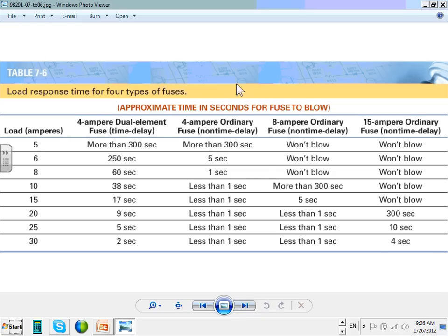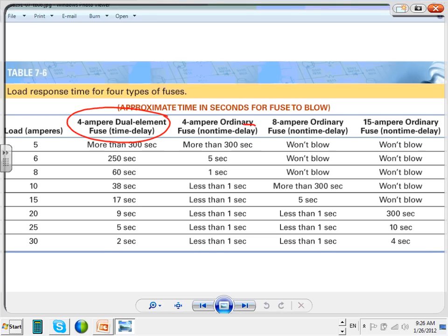This is just how fast the overcurrent protective device can trip, guys. Dual element time delay fuse, non-time delay fuse, ordinary non-time delay fuse. So time delay, it trips at 250 seconds. If you don't have a time delay, Chris, it trips at what? 5 seconds. I promise you we're going to get into this one when you do the coordination. Remember that curve that I drew? That's how it's going to make the slope of that curve. That's why when we size this guy, we multiply by 300%. When we size this one, we multiply by 170% from the code.